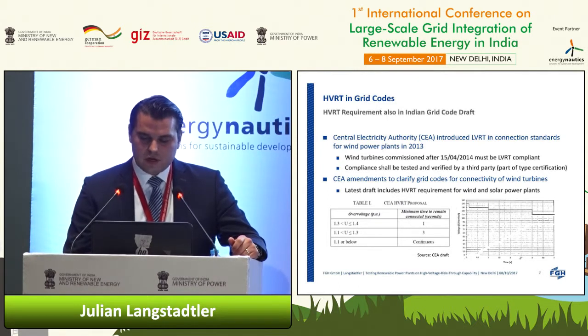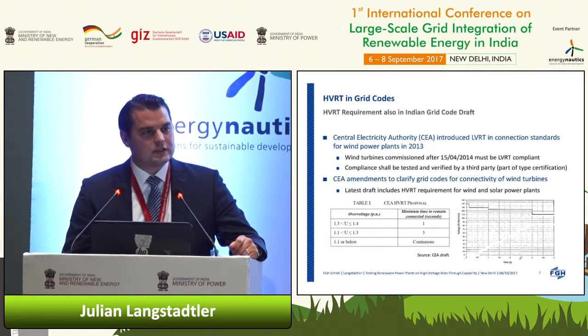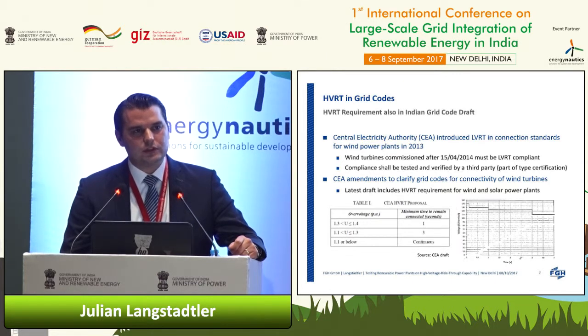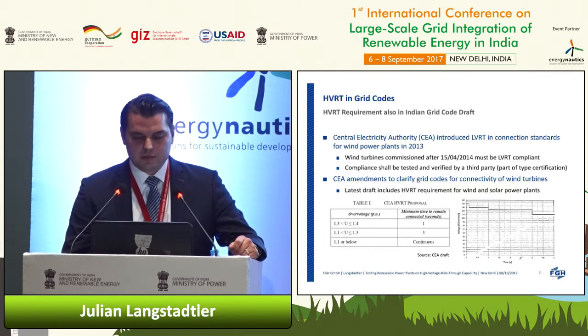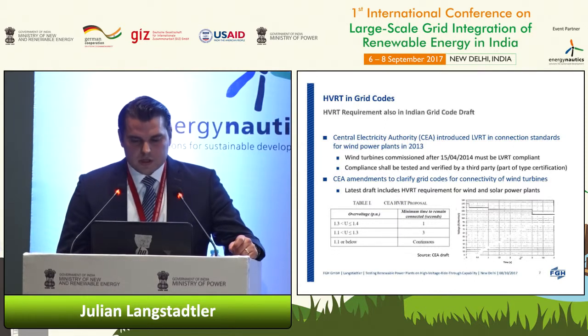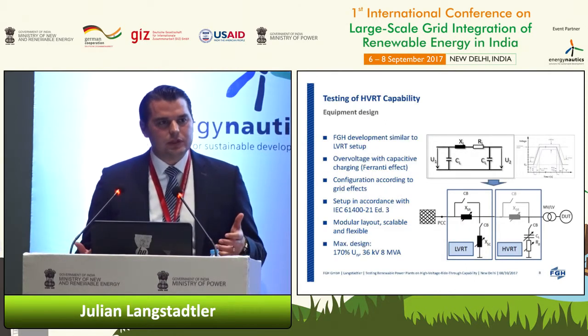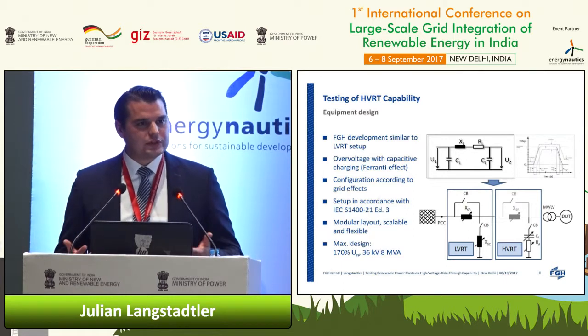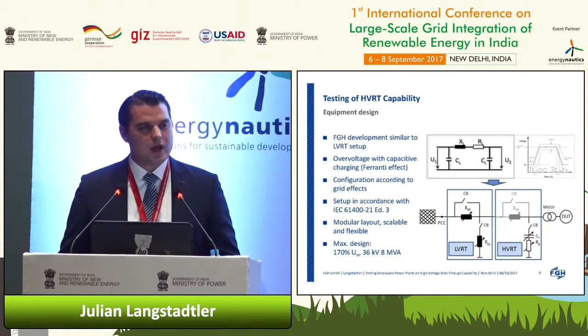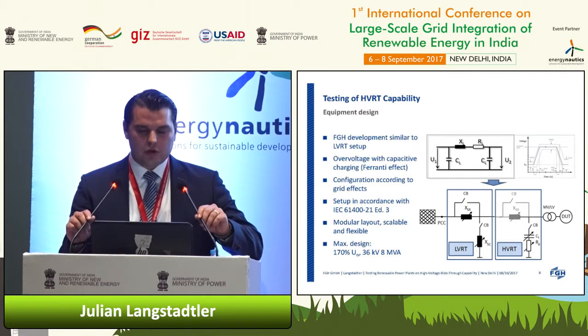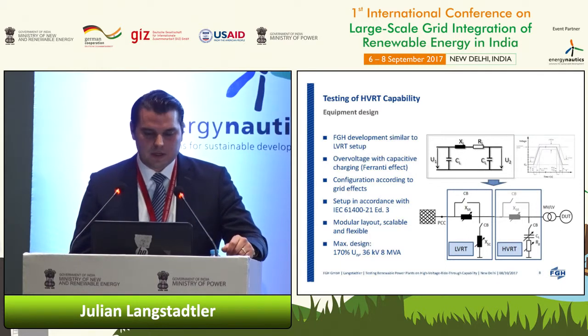And I've shown here, just taken from the draft version, the voltage against time profile, where you see that even voltages up to 140% of nominal voltage here in India are supposed to be fault ride through capable. So when you've got such requirements in the grid codes, you must have a procedure how to test them. And in order to have a procedure, you also need equipment to test them.